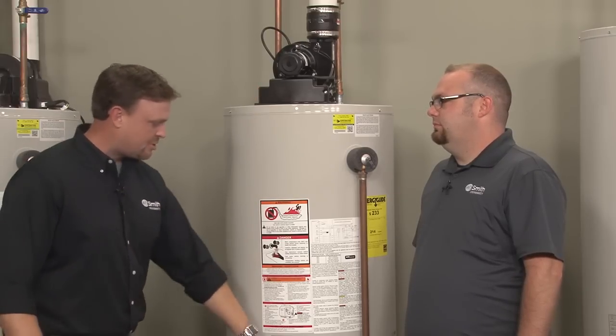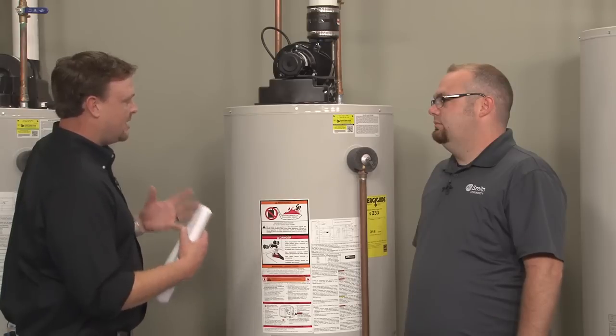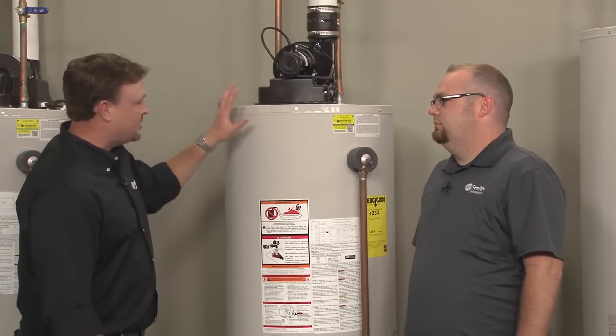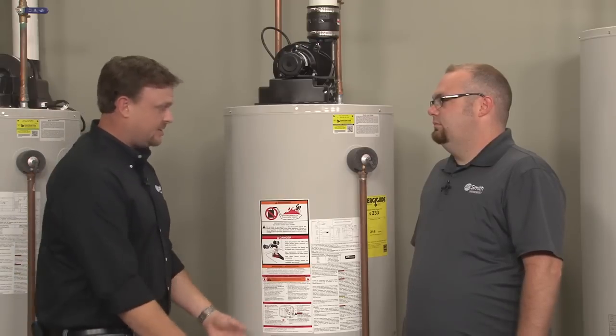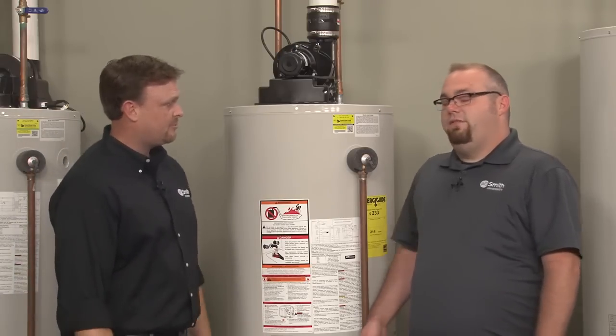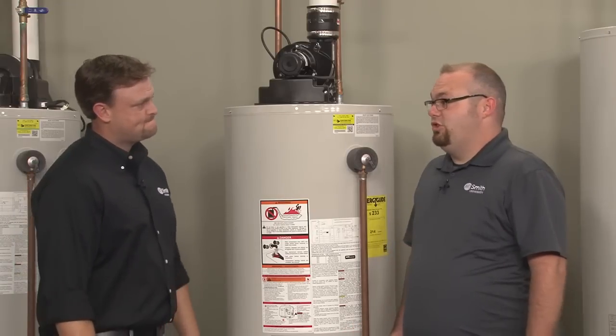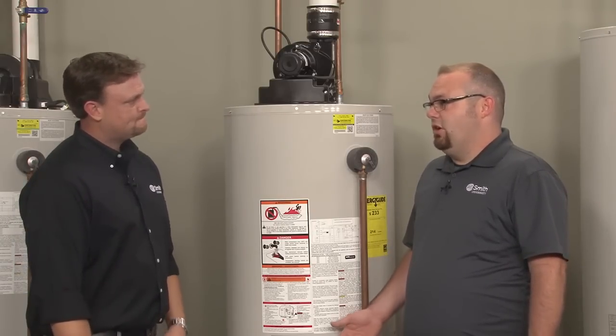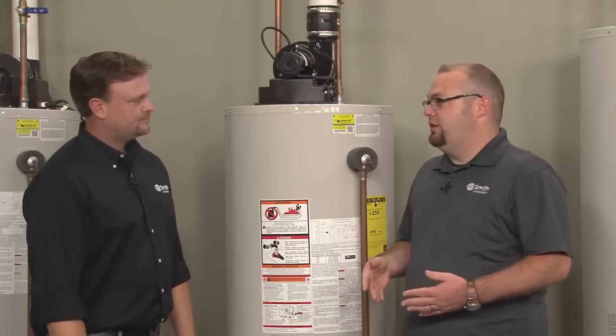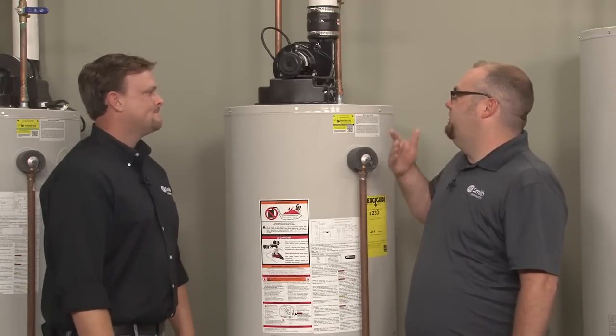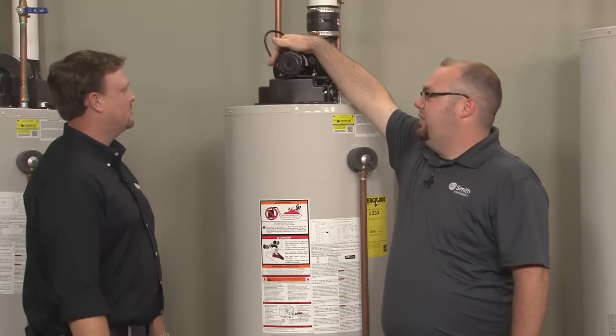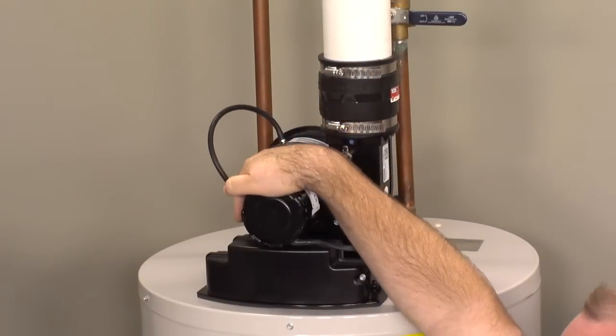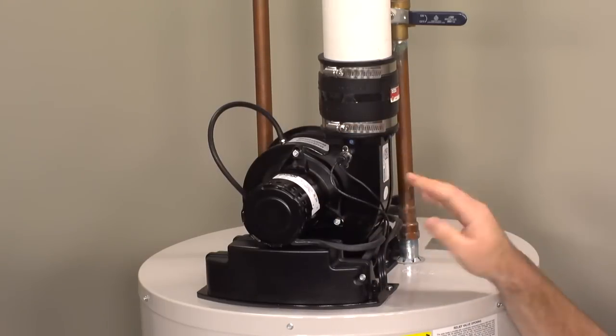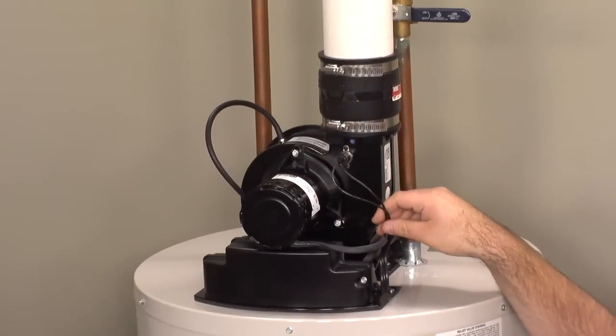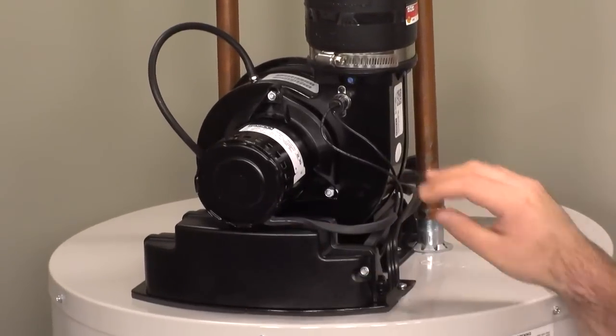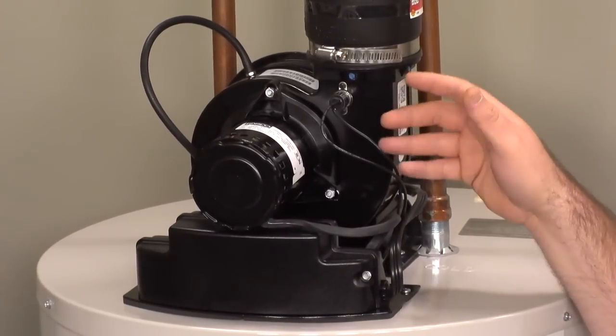Now, what if I walk up to it, turn it off, and turn it back on, and I've got an error code 3? The blower starts, but I continue to get that 3 code. Well, the first thing I like to do is simple visual checks. Anytime I'm troubleshooting a code where the air pressure switch is not closing as it's supposed to, I check stuff visually. First thing I check is my sensing tube, to make sure it's hooked up. It needs to be hooked up on both sides. I make sure I don't see any damage to any wiring, which is kind of hard to see on the newer units, since all the wiring's enclosed in here. It shouldn't be a problem, but I like to double check it.